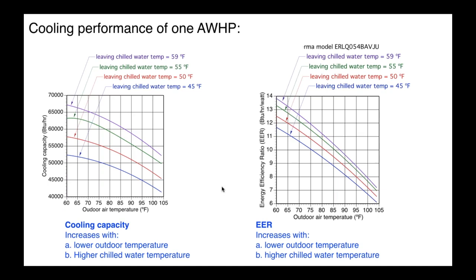Performance of the heat pump on chill water cooling, bottom line, the colder you want the water, the lower the performance of the heat pump. It's just the opposite of heating performance. So if we can operate our cooling system with, let's say, 55 degree chill water versus 45 degree chill water, a substantial difference in cooling capacity. And we also get a substantial difference in energy efficiency ratio, in effect, the cooling equivalent of COP.